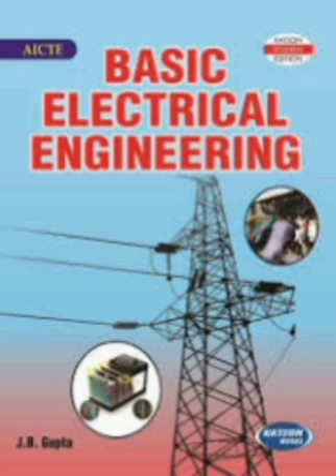Open circuit test and short circuit test. These two tests on transformer help to determine the parameters of the equivalent circuit, voltage regulation and efficiency. They help in predicting performance of the transformer without actually loading it. Open circuit OC test: main objectives of the test are to find out parameters of no load branch, that is R0 and XM of the equivalent circuit.